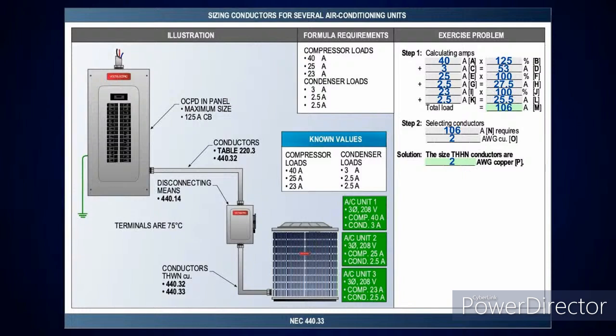Then I take the 25 amps and the 2.5 at 100%. That gives me 27.5. Then I have the 23 amp and 2.5 amp for AC unit number 3, and that'll give me 25.5 amps, and that all was taken at 100%. So I still only took the largest. Everything else at 100% gives me 106 amps.